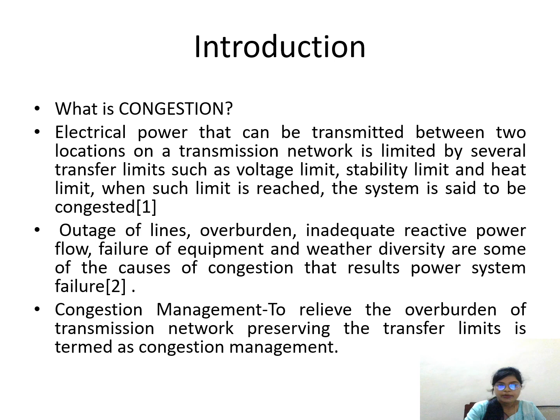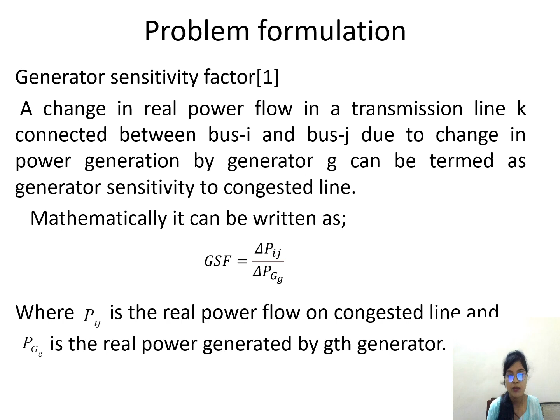For congestion management, three conventional methods are generator rescheduling, load shedding, and extension of new transmission lines. From an economic point of view, the generator rescheduling method is mostly used for congestion management, which is based on the GSF values. GSF is the generator sensitivity factor, which represents a change in real power flow in a transmission line K connected between bus I and bus J due to the change in power generation by generator G. Generators are selected on the basis of their non-uniform GSF values.